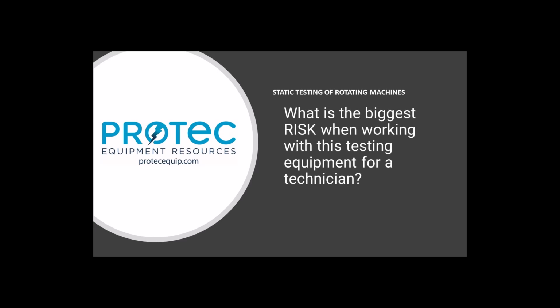As I brought up in the webinar, when you are testing motors, you are testing large inductors. Coils are big inductors, and they store energy in the form of magnetic fields. So if you're doing winding resistance tests and you're pumping DC current into this winding, you are creating a huge magnetic field. Now, after the test, if you're using proper test equipment, most have discharge mechanisms built in to help collapse that field safely and take down the stored energy.